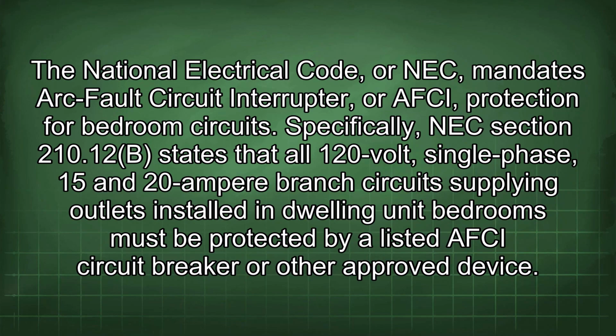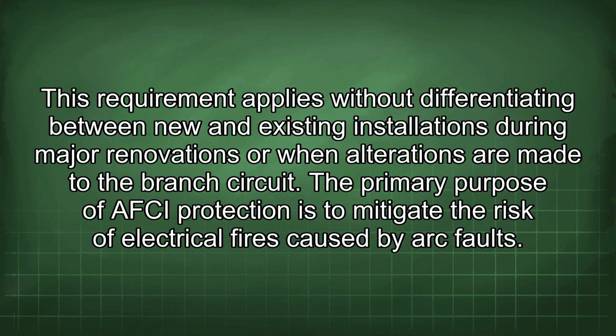The National Electrical Code, or NEC, mandates arc fault circuit interrupter, or AFCI, protection for bedroom circuits. Specifically, NEC Section 210.12(B) states that all 120-volt single-phase 15 and 20-ampere branch circuits supplying outlets installed in dwelling unit bedrooms must be protected by a listed AFCI circuit breaker or other approved device. This requirement applies without differentiating between new and existing installations during major renovations or when alterations are made to the branch circuit. The primary purpose of AFCI protection is to mitigate the risk of electrical fires caused by arc faults.